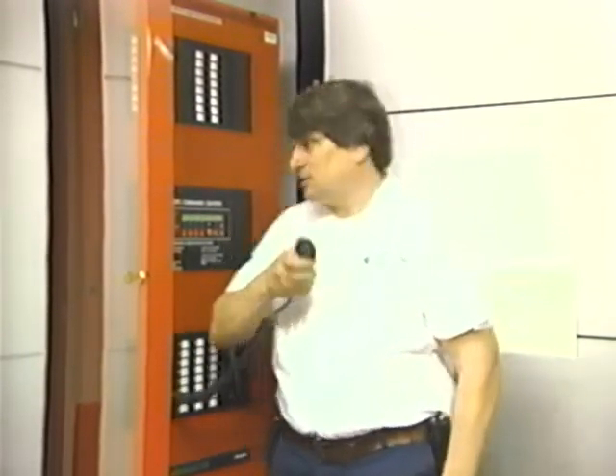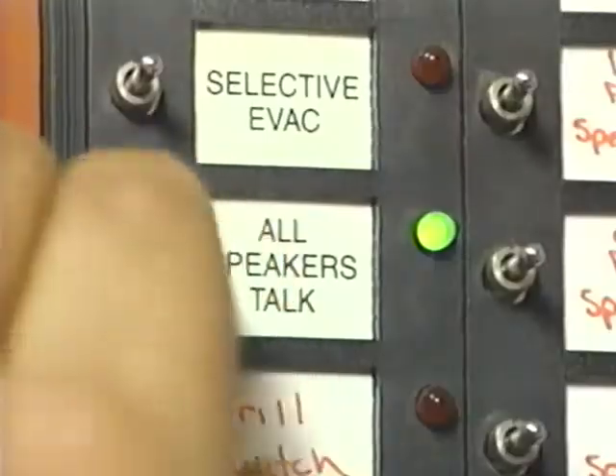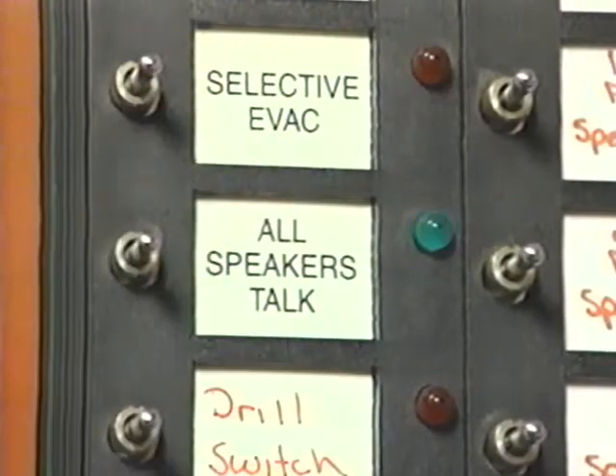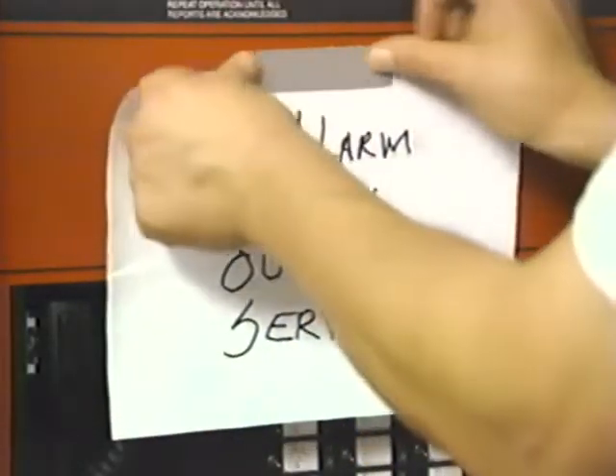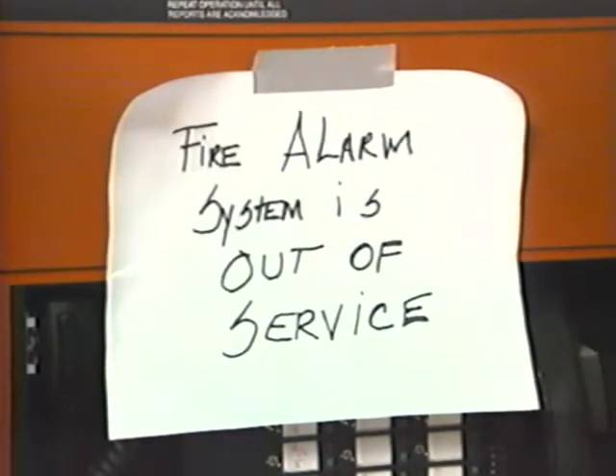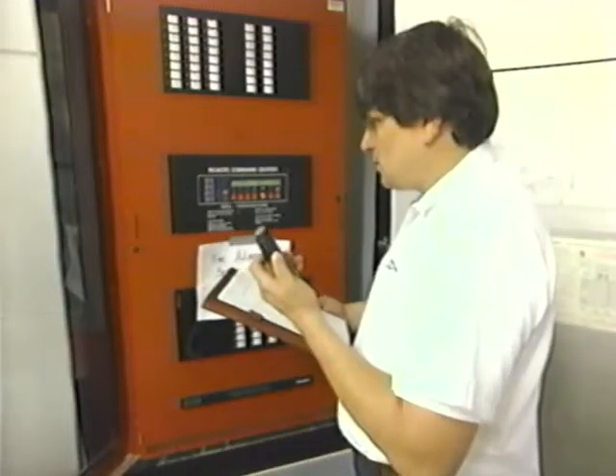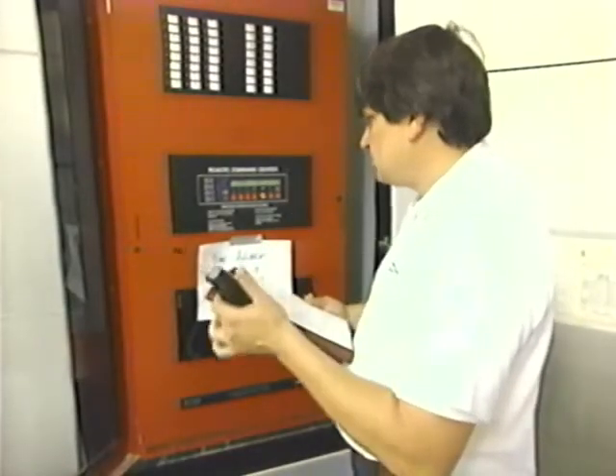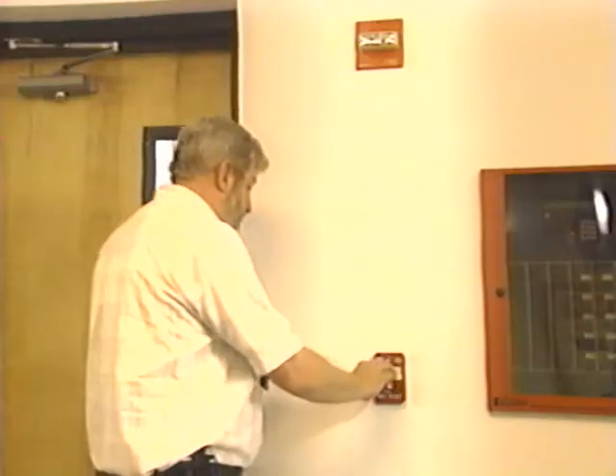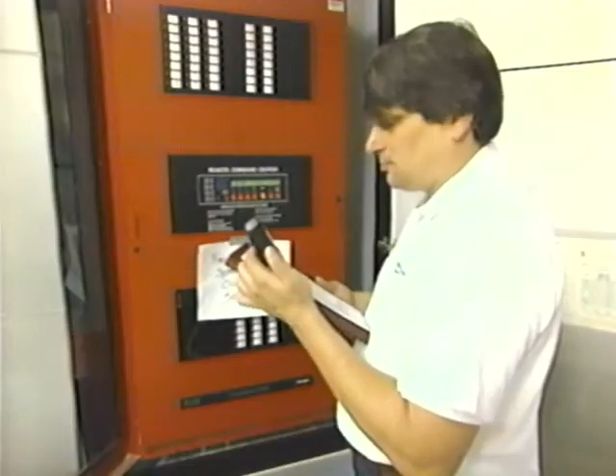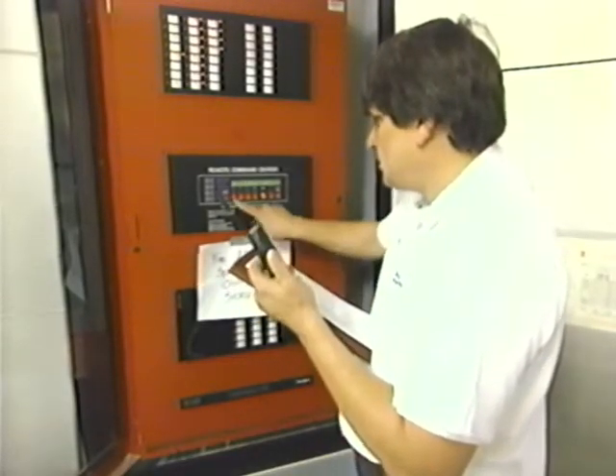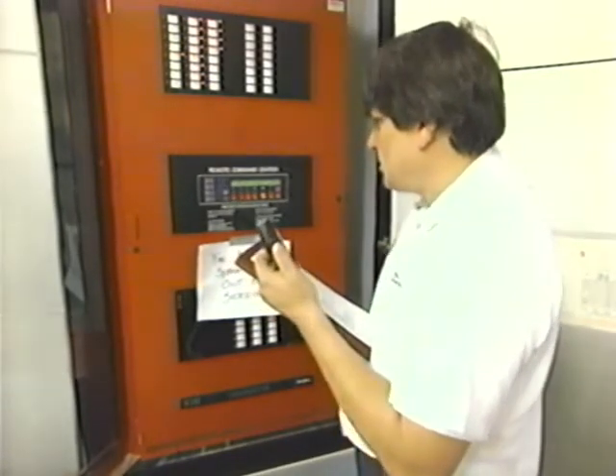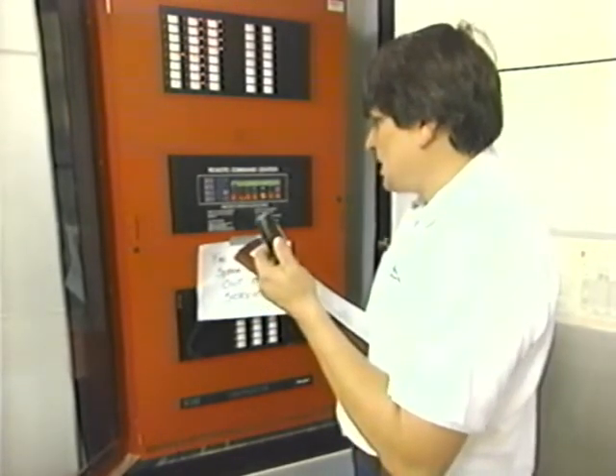Another solution is to disable the system. Make sure that all concerned parties, such as the fire department and security personnel, know that the system is disabled. Maintain a presence at the control unit for the entire time the system is disabled, and maintain constant communication between that person and personnel working in the field.